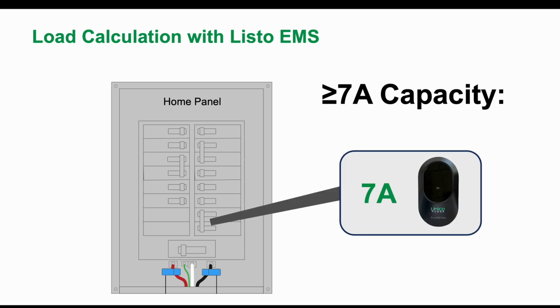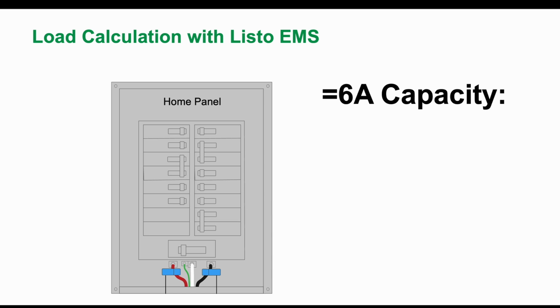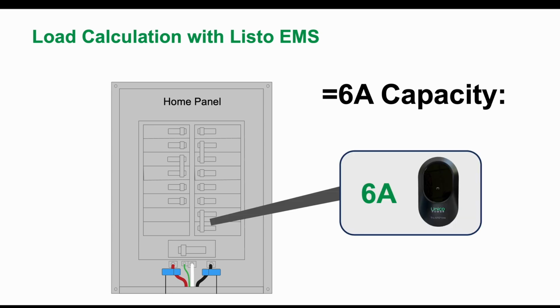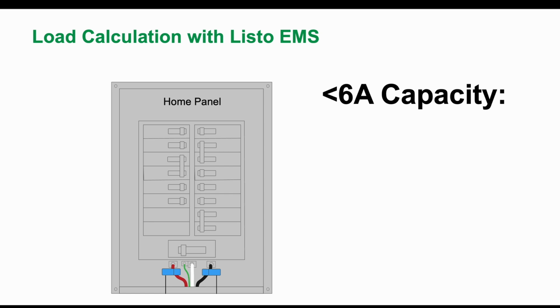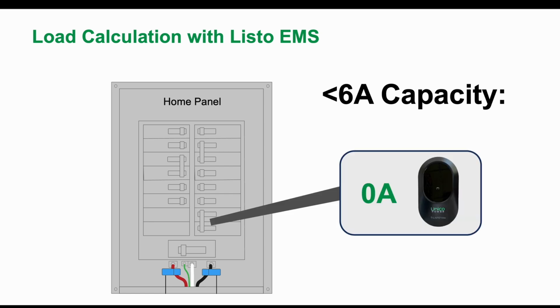In this case, when there is greater than or equal to 7 amps of capacity available, the EV charging load is considered a 7-amp continuous load on the residential load calculation. If there is 6 amps of capacity available, the fail-safe limit and continuous load are set to 6 amps. When there is less than 6 amps of capacity on the panel, the fail-safe limit is set to 0 amps, and the EV charging load will be throttled down to 0 amps when necessary.